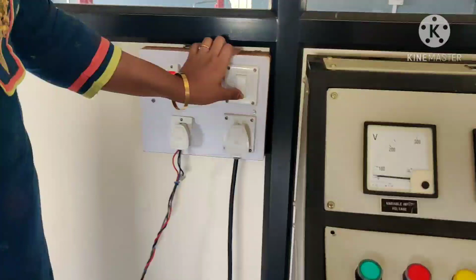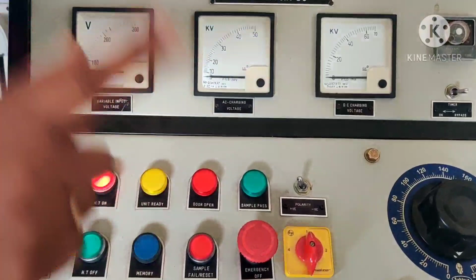Unit ready is on. Right, now until and unless we make HT on, there will be no transforming up of the voltage ratio from 230 volts to either 50 kilovolt AC or DC, until and unless we turn on the HT.